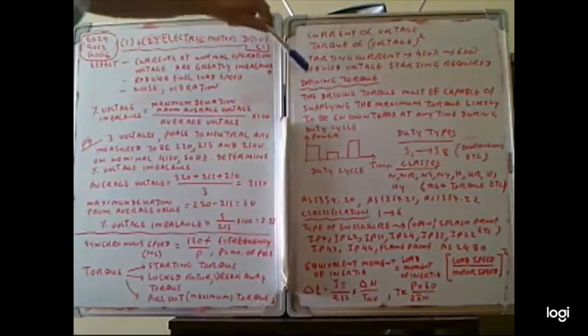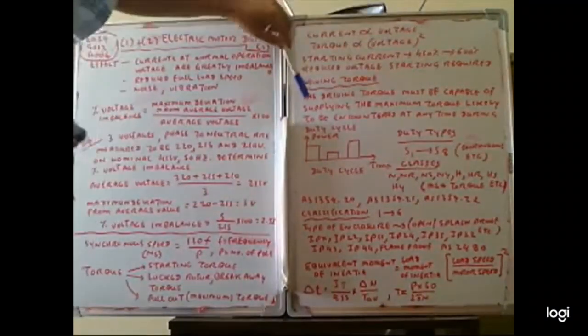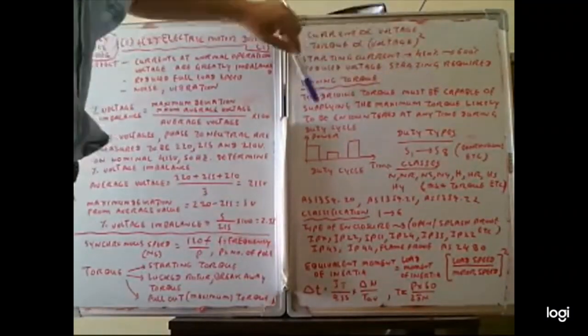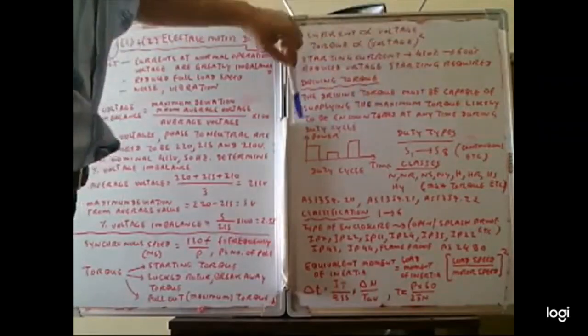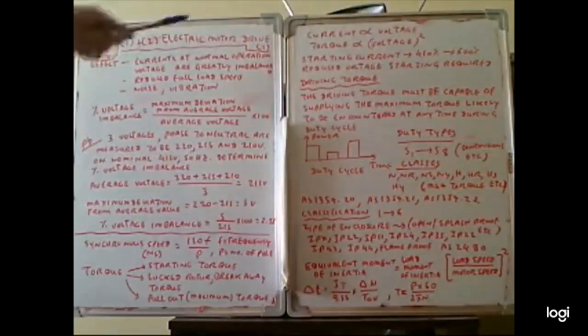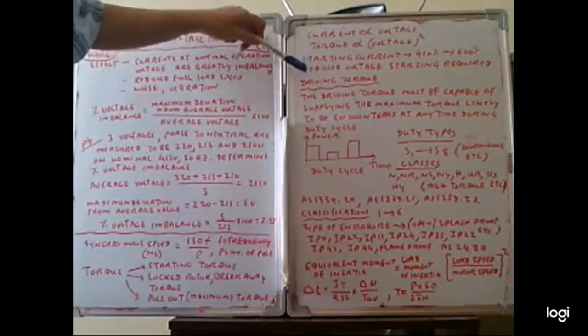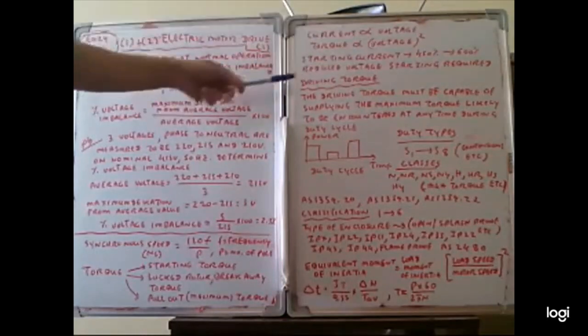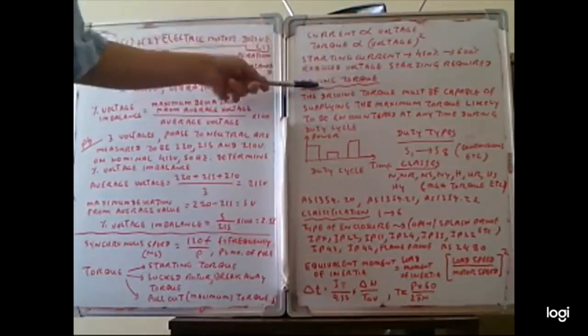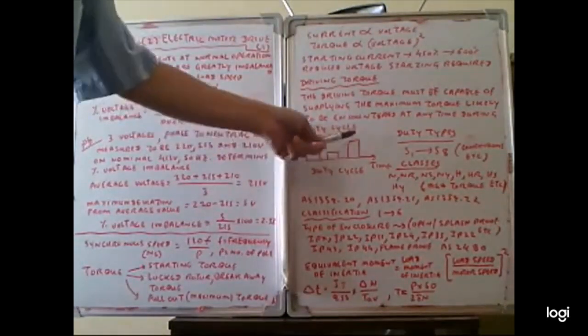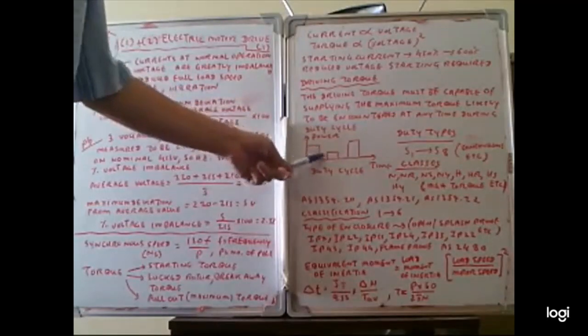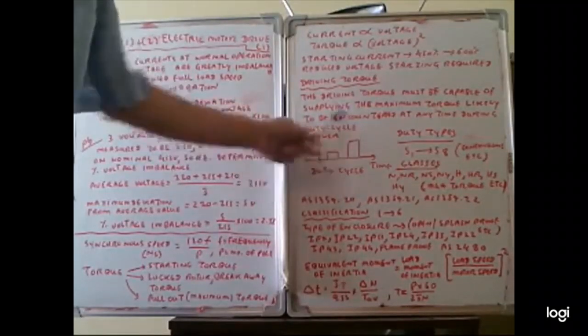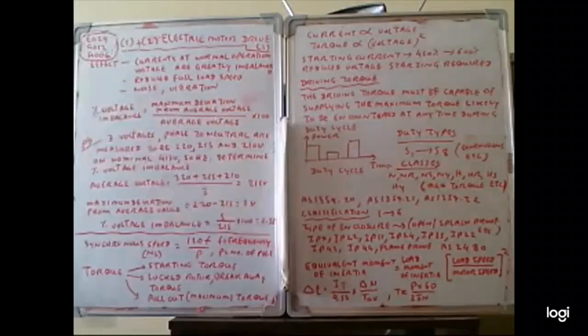The driving torque must be capable of supplying the maximum torque likely to be encountered at any time during the speed cycle. When the motor is running, sometimes the load torque can be higher. In this case, the motor must have the appropriate driving torque to overcome the load. Otherwise, the motor will stop. So sometimes motors are running, sometimes motors are stopping. The motor run and stop happening frequently is what we call the duty cycle.